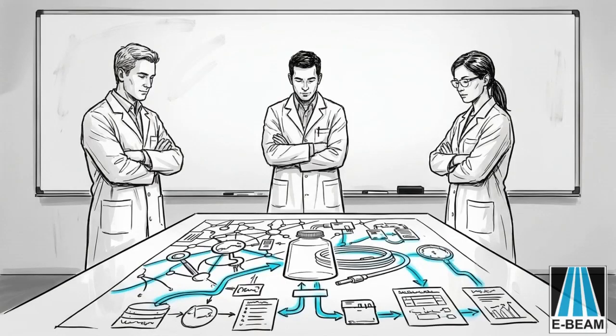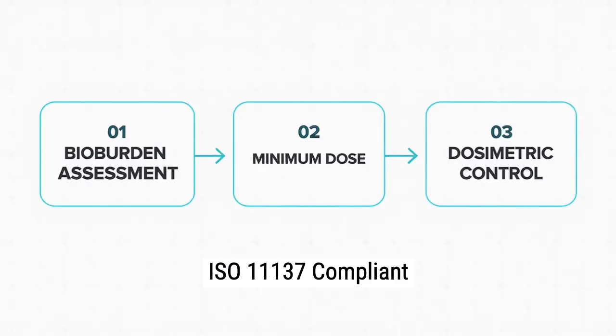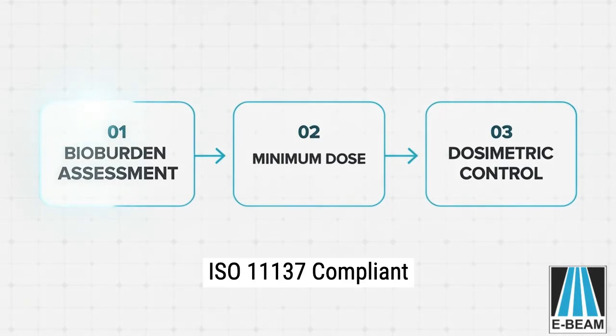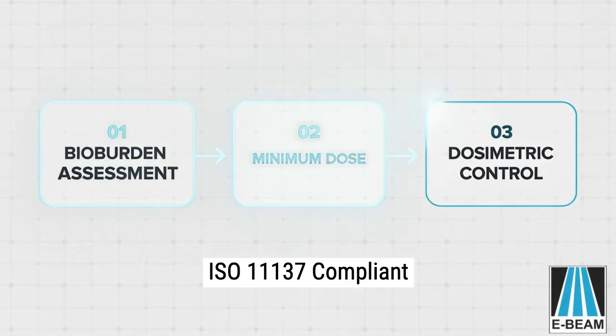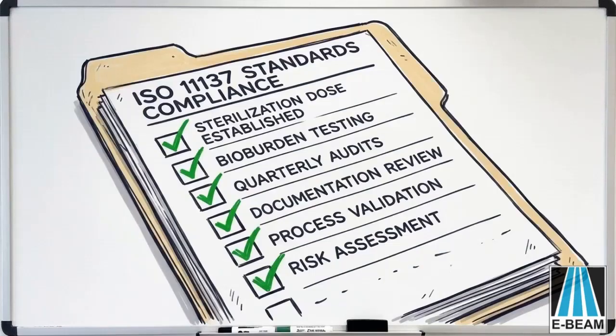So what actually changed when this product moved to ebeam? Validation got simpler. Instead of iterating on a complex gas cycle, the team focused on bioburden, minimum sterilization dose, and dosimetric control, using recognized ISO 11137 methods.